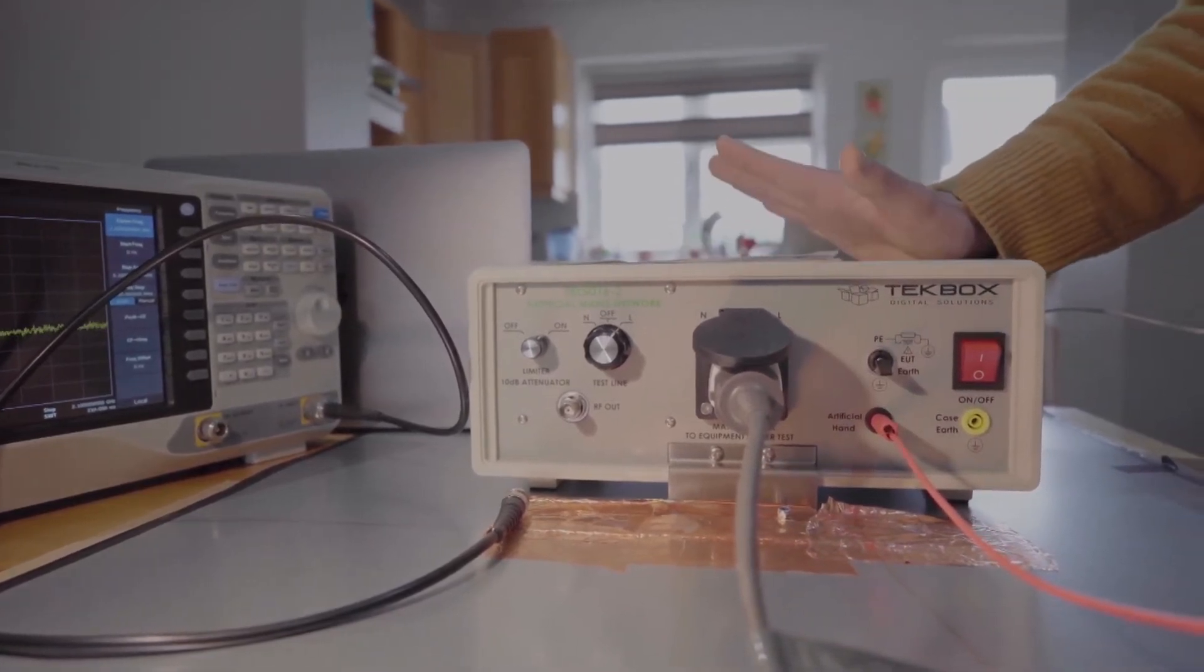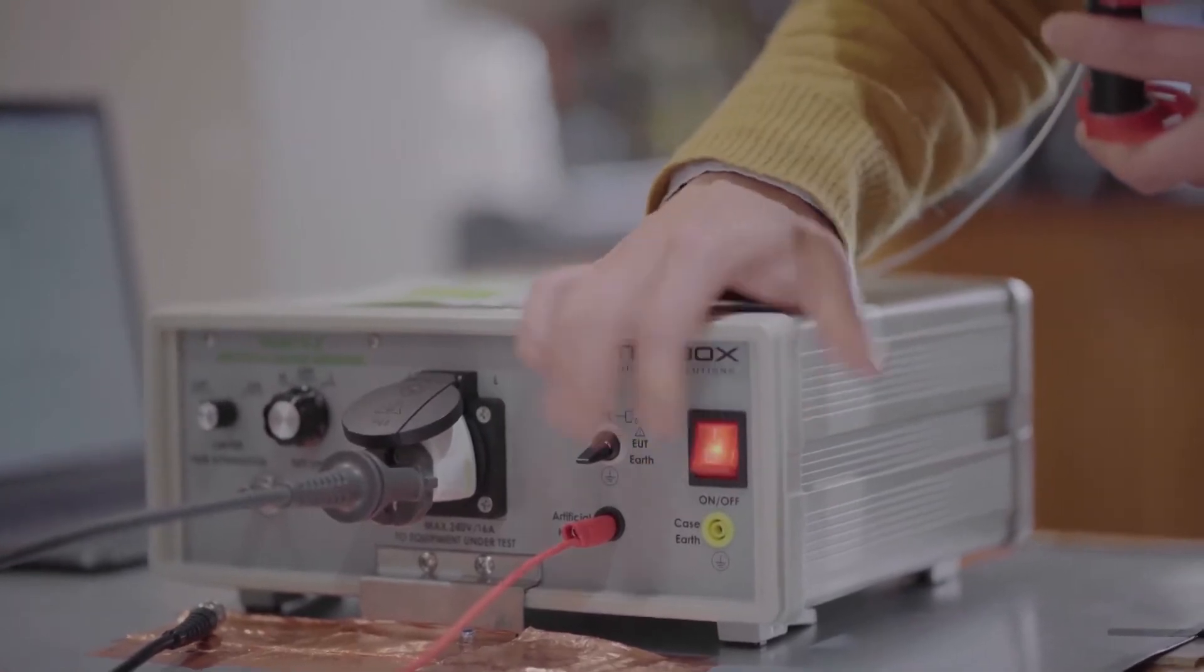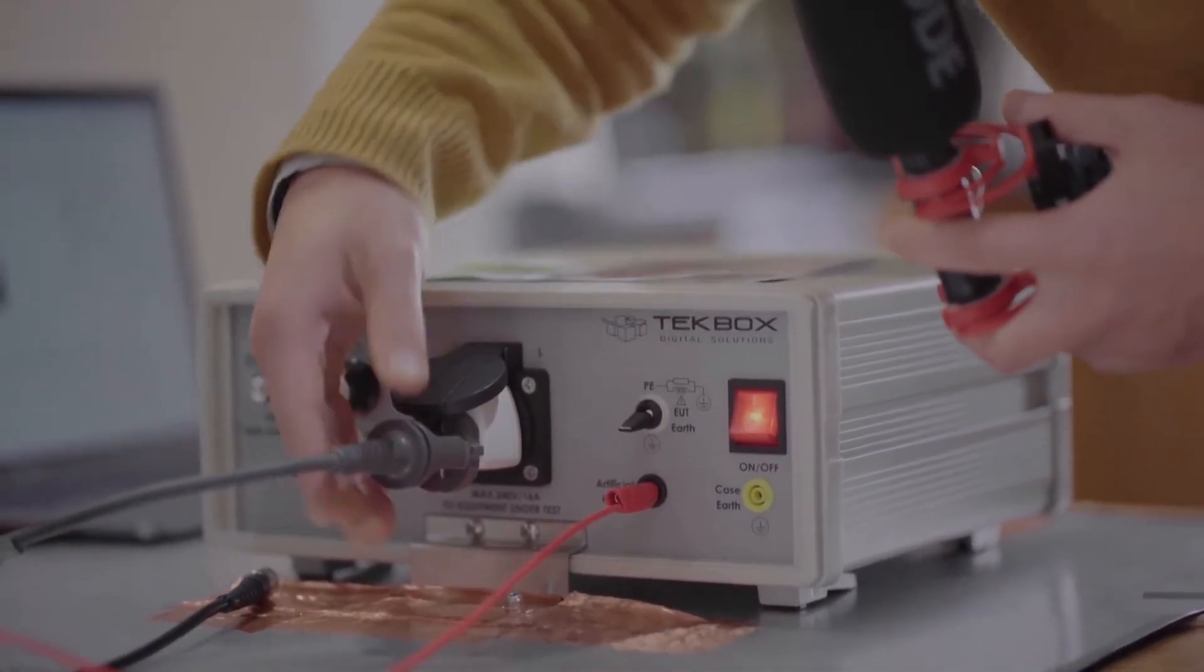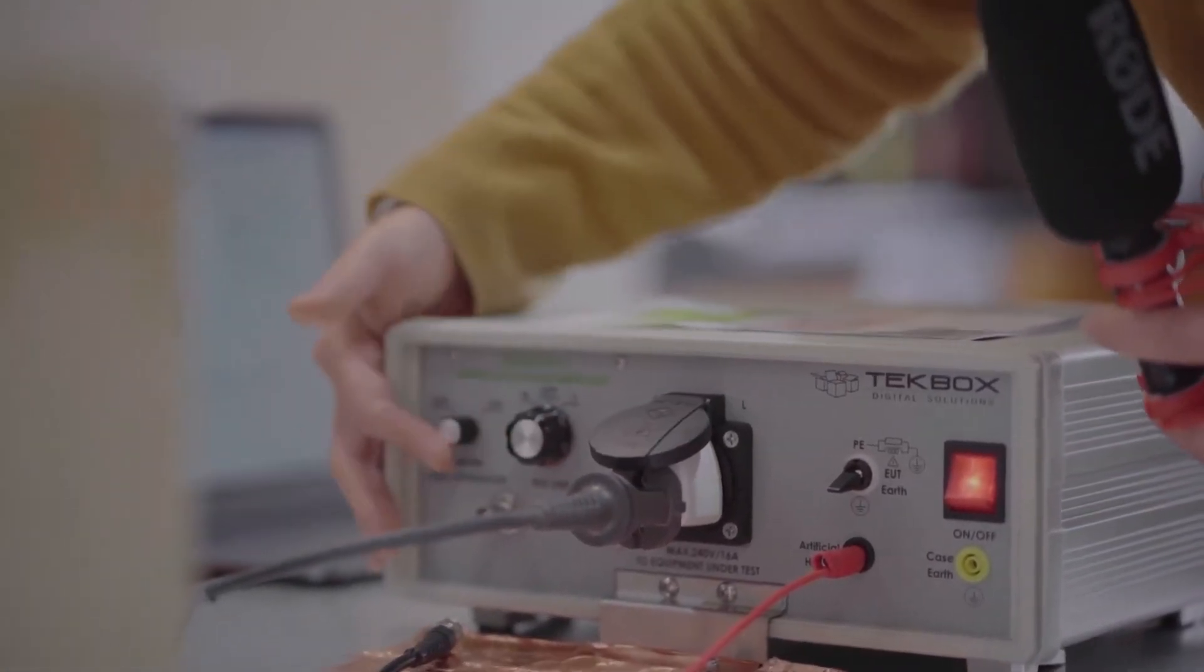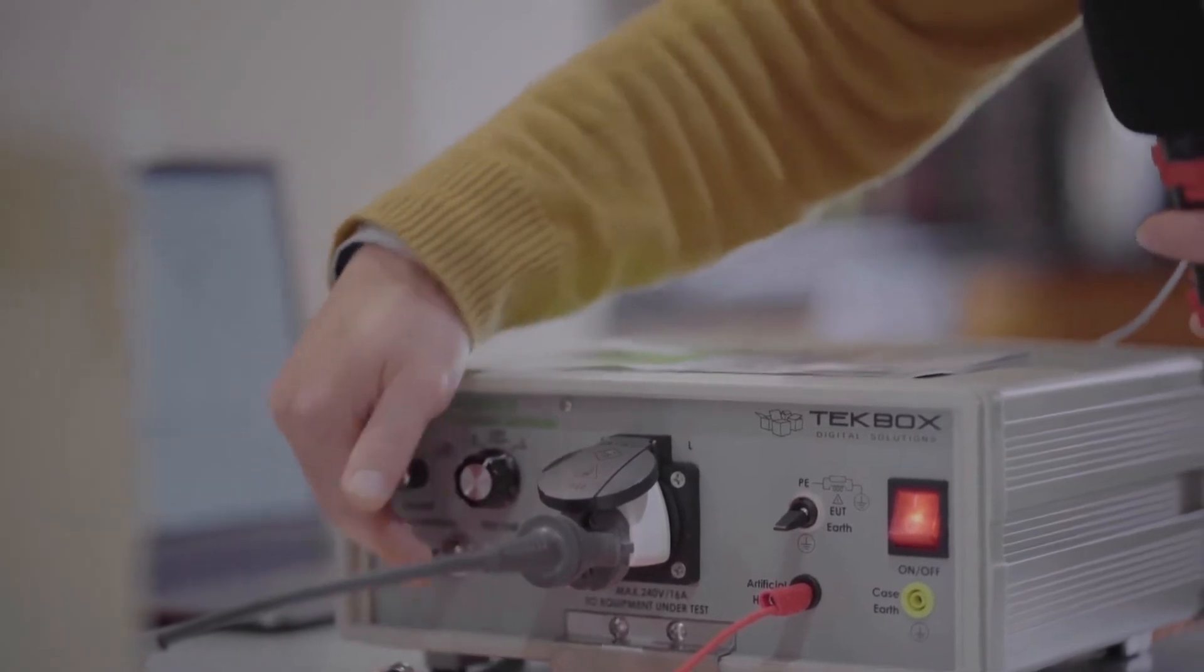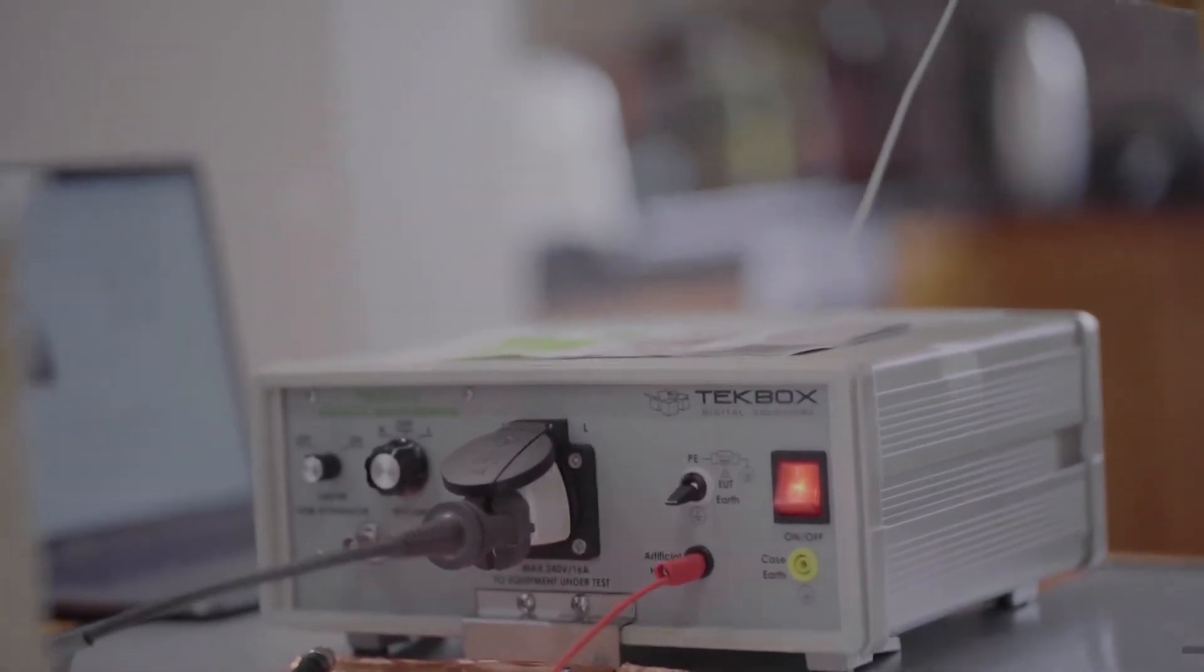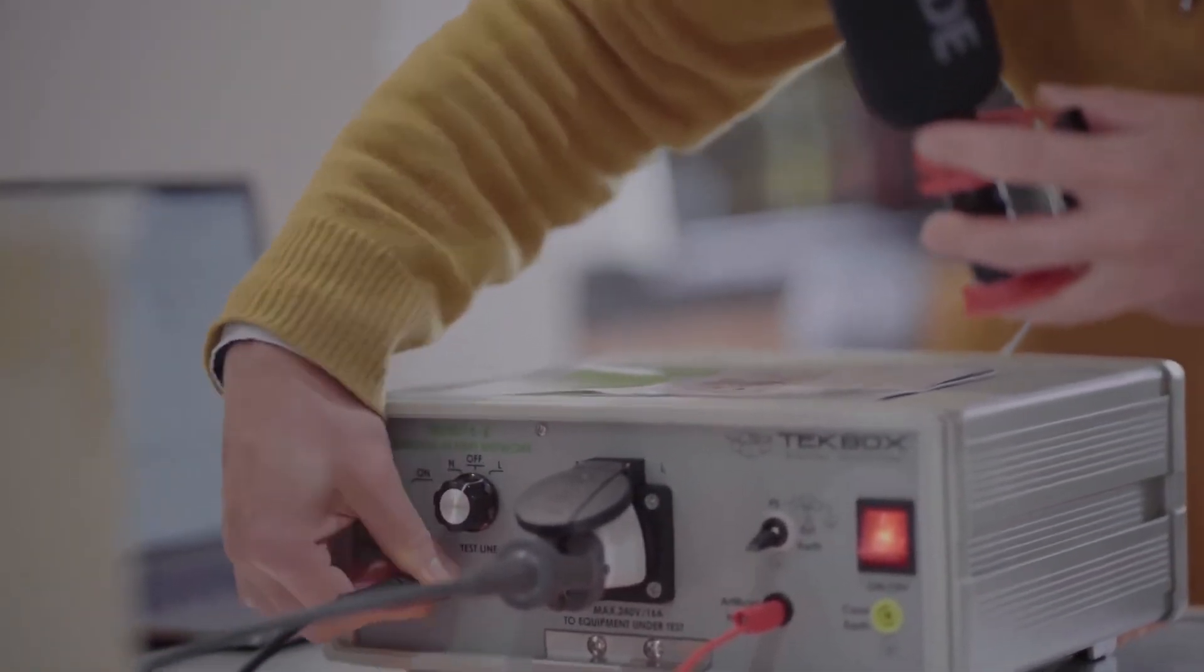Now we are going to have the product tested. Everything is set up. Switch on the LISN. You can see the light is on and we make sure artificial hand is connected, power cable connected. We're going to measure the conducted emission on the live line. Then I turn the attenuator off because I already checked the RF output. I need to switch on the product first. Turn on the product. Now I'm going to connect my spectrum analyzer.